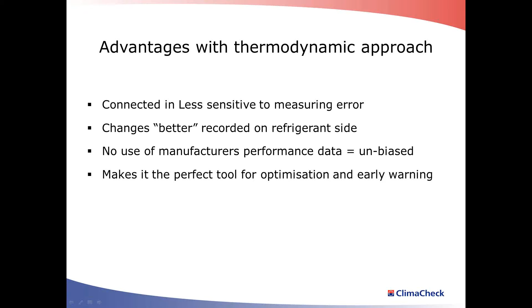This is just an energy optimization project that was done on 6 Carrefour supermarkets in Italy, where they mounted the ClimaCheck equipment for fixed monitoring, and then they worked systematically to optimize the controls of the systems and correct errors in systems. And they reduced their electrical consumption by 23%, which in this case corresponded to 318,000 euro per year saving, which was much more than the total installation cost.